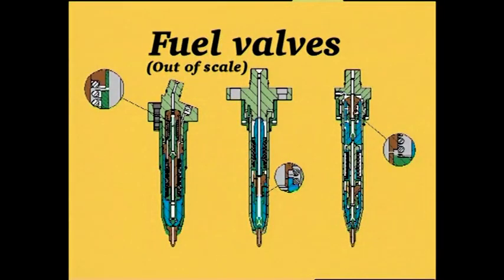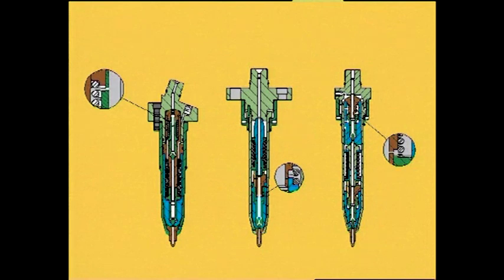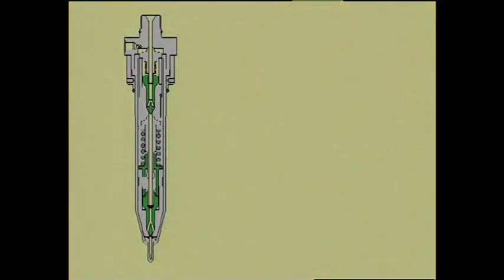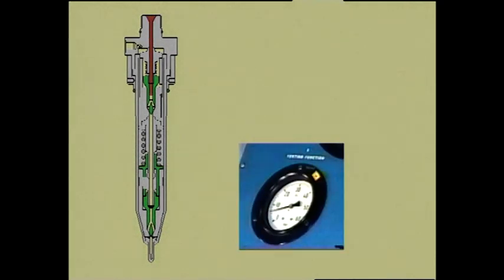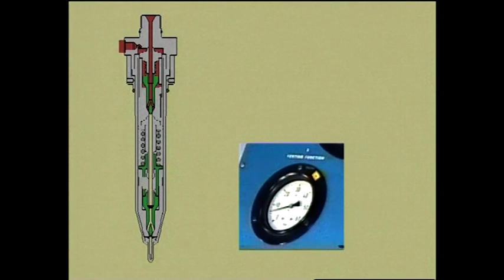Fuel valves are available in three different designs depending on engine size. Refer to your instruction book to see which valve is to be used on your engine. The pressure testing procedure is the same for all types of valve. Slowly fill the valve by pumping at low pressure until fuel oil, without air bubbles, flows from the fuel oil return pipe.